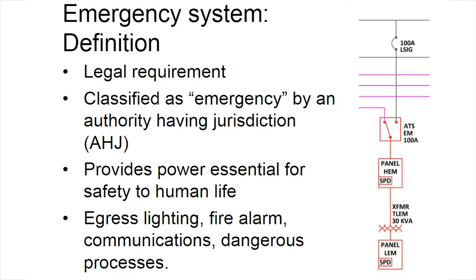Some systems that we might intuitively think of as emergency loads aren't, in fact, code-designated emergency loads. Smoke removal systems aren't on the list of emergency loads, and in fact, they're served as legally required standby.